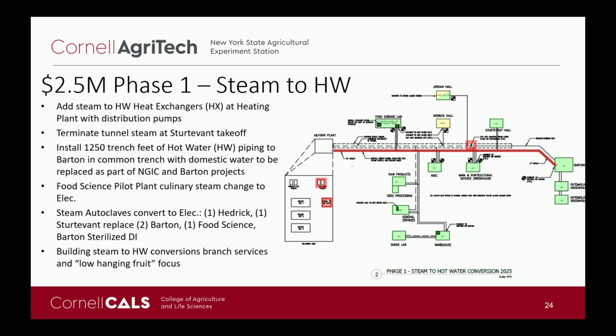There's 1,250 feet of that included in our first step toward implementation. That would allow us to pull steam distribution back to about 50% of the tunnel length, significantly changing our heat loss through the tunnel when it is operating. We'd also take a stab at the culinary steam in the food science building, getting that converted to electric.